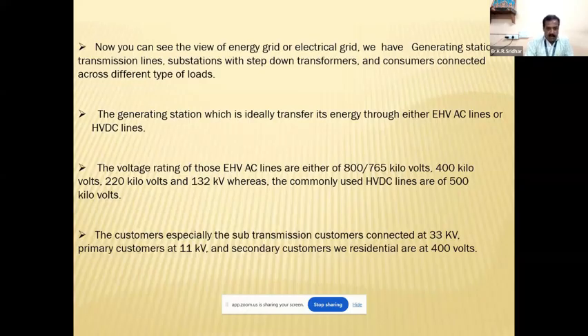The voltage rating of EHV lines is either 800 or 765 kilovolts, 400 kilovolts AC, 220 kilovolts, and 132 kilovolts. Commonly used HVDC lines are 500 kilovolts. So we may use either EHV AC lines or HVDC lines, normally used for transmission lines. Customers, especially sub-transmission consumers, are connected with 33 kV lines, primary customers at 11 kV lines. The secondary customers, our end users like residential people, use 400 volts or 230 volts.